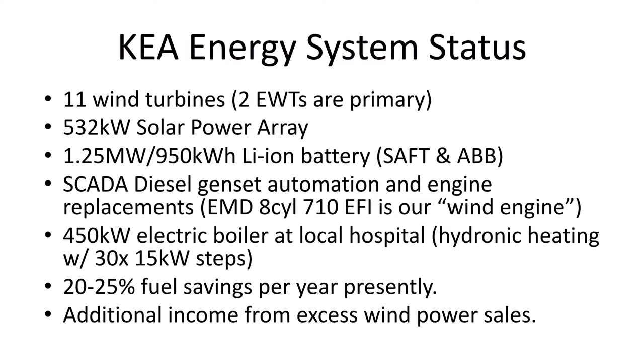Since 2015 we've had a lithium ion battery here as well. It's 1.25 megawatts, so it can only supply about a third of the town's power. Right now we're using it essentially for spinning reserve. It helps us with outage mitigation and helps us keep the system up and running—another term is renewables firming. So when we have a loss of a wind turbine or something, the battery helps keep the power on and helps the diesel keep the system up.